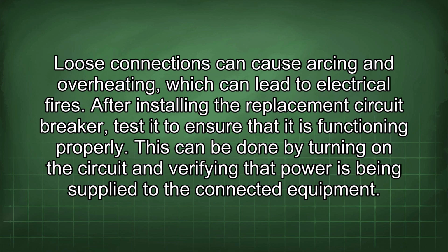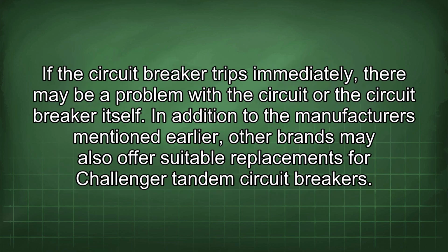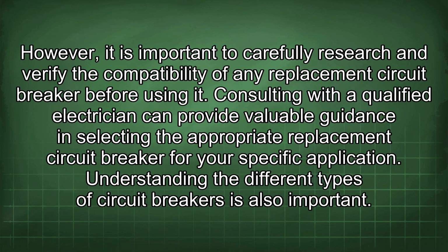After installing the replacement circuit breaker, test it to ensure that it is functioning properly. This can be done by turning on the circuit and verifying that power is being supplied to the connected equipment. If the circuit breaker trips immediately, there may be a problem with the circuit or the circuit breaker itself. In addition to the manufacturers mentioned earlier, other brands may also offer suitable replacements for Challenger tandem circuit breakers. However, it is important to carefully research and verify the compatibility of any replacement circuit breaker before using it. Consulting with a qualified electrician can provide valuable guidance in selecting the appropriate replacement circuit breaker for your specific application.